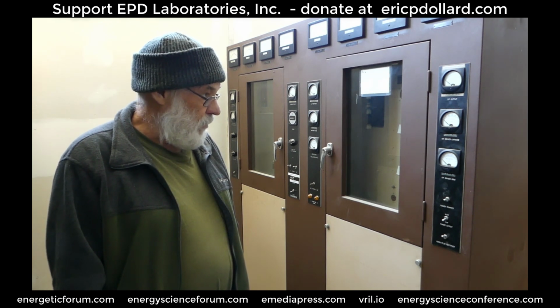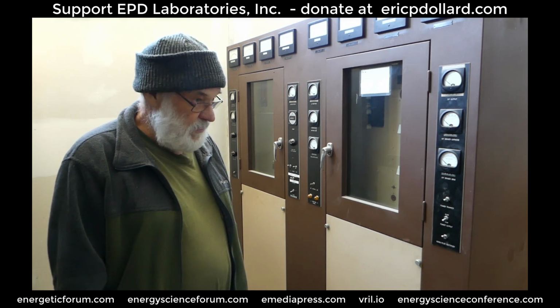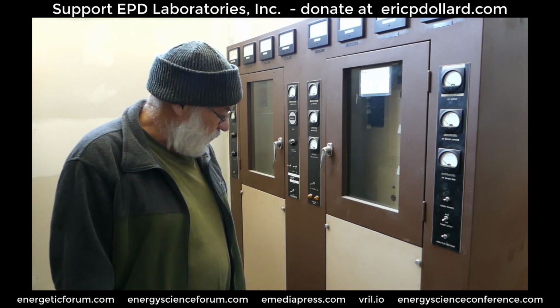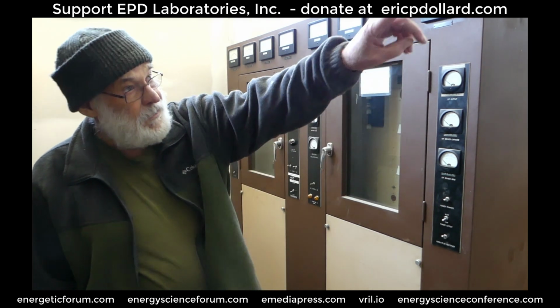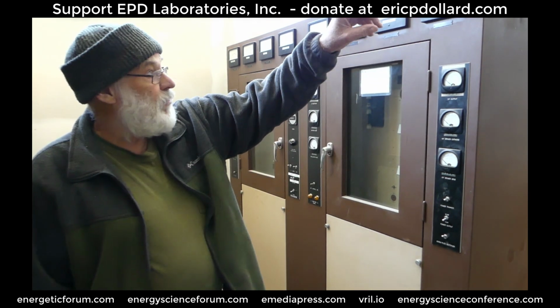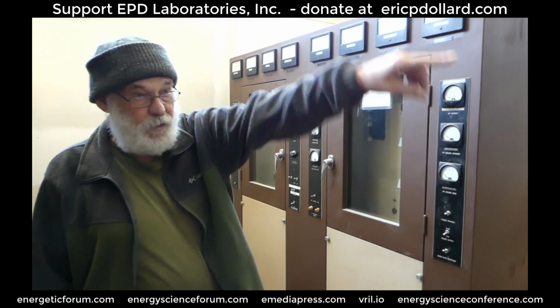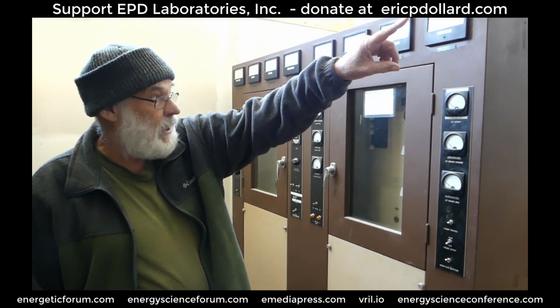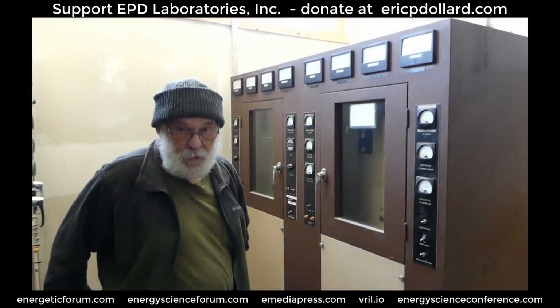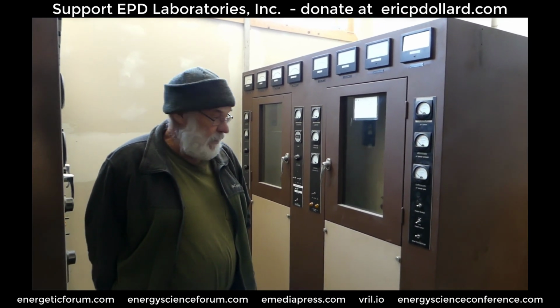So what I plan to do, which isn't the best thing in the world, is to pull the rectifiers out completely and put them in the power room. That way, rather than having a three-phase 100 amp run — all the copper involved coming from where power enters the building, on the exact opposite side, over to here — all that pipe and wire will be reduced greatly in size.